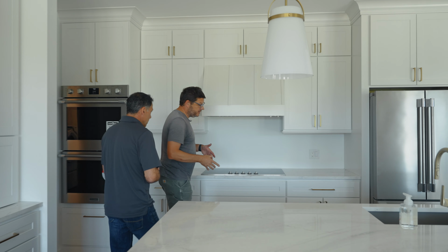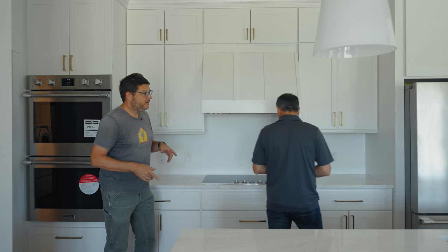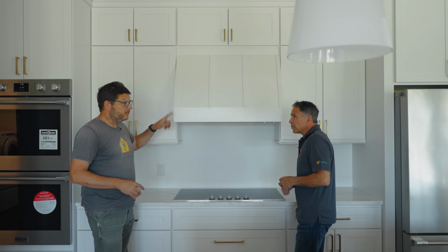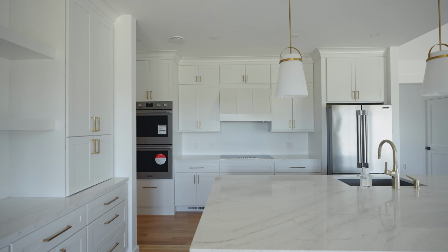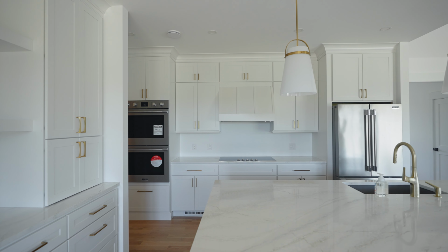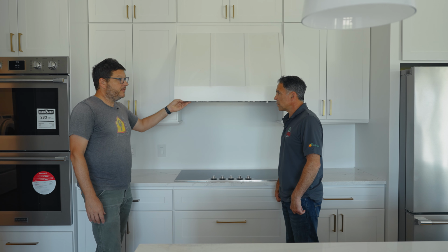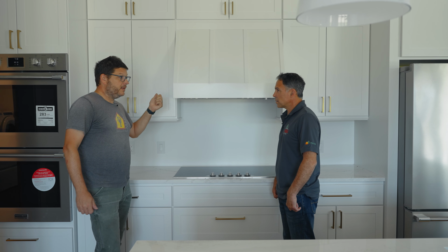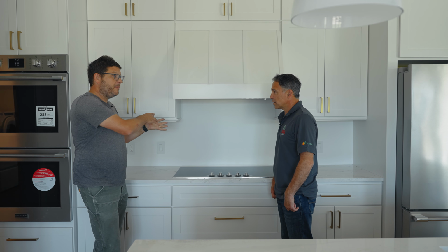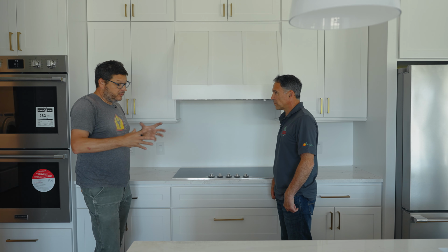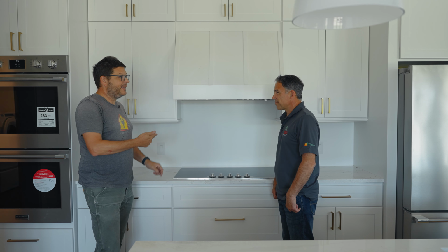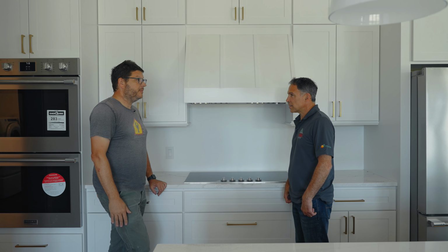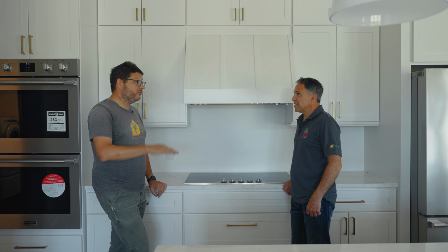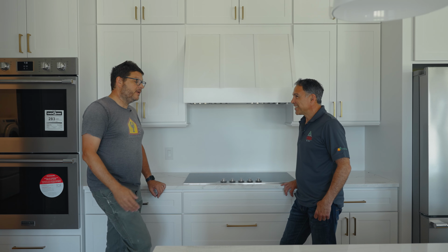When we first started building these houses, we didn't do an exhaust range hood. We always did recirculating, because one of the things we were concerned about is when you build a really airtight house, and let's say you put a 300 CFM range hood in, you turn it on, it's trying to push 300 CFM out, but that house is so airtight, there's no place for that air to come back in. There's no makeup air. In the residential building code, as soon as you get above 400 CFM, you're supposed to put in makeup air. Okay. Nobody does. People are starting to, but for you, I rarely ever see it.